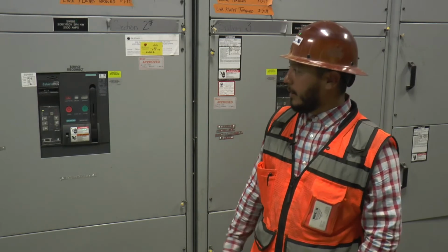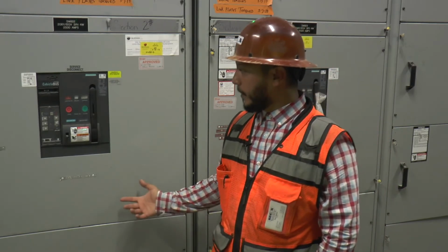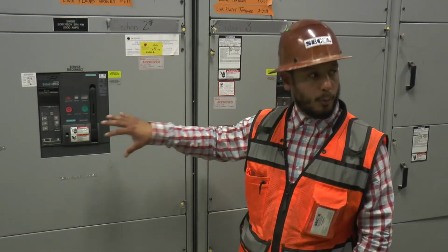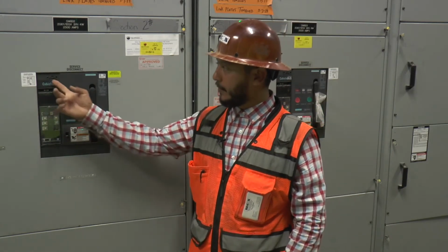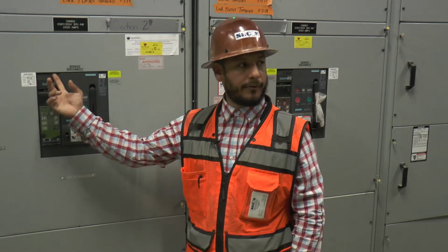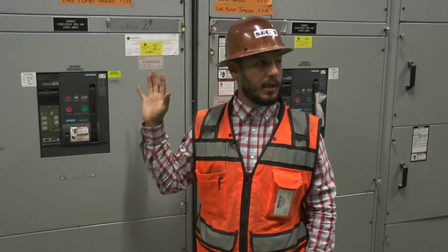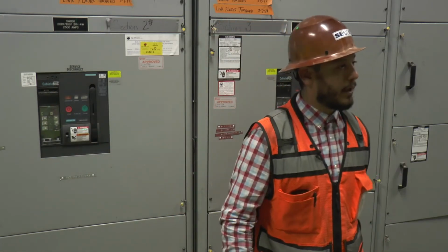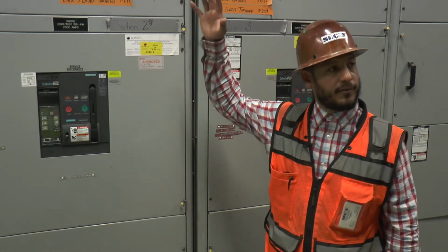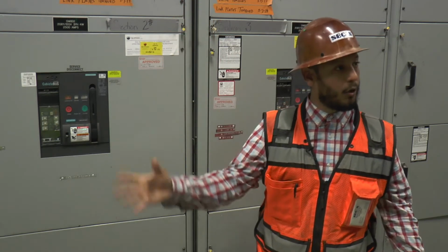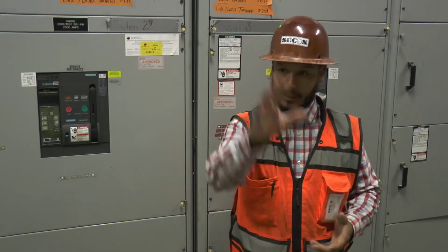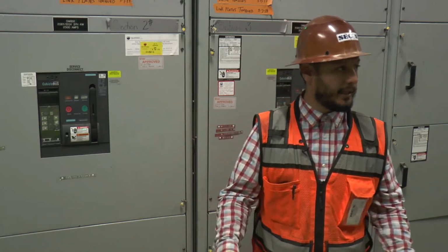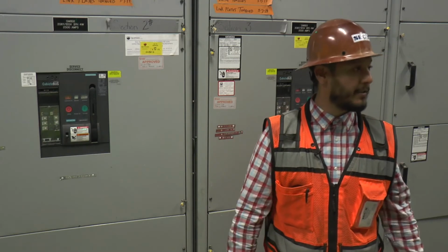In order to lock it out, you would have to open the circuit. This would be the lever to then release your lockout tagout if for any reason you need to service from this section to the tap box. If anything needs to be serviced from the meter sections, they have their own lockout breaker that you could lock out there, and they could service any meter sockets that they need or pull them or whatever they need to de-energize.